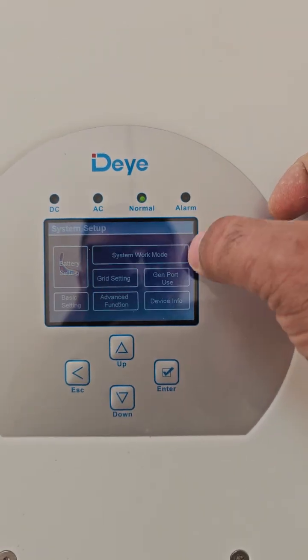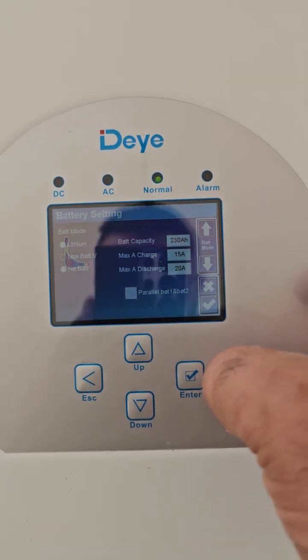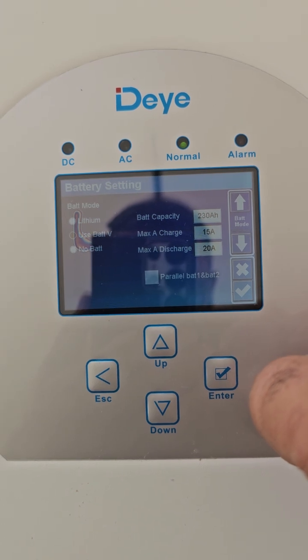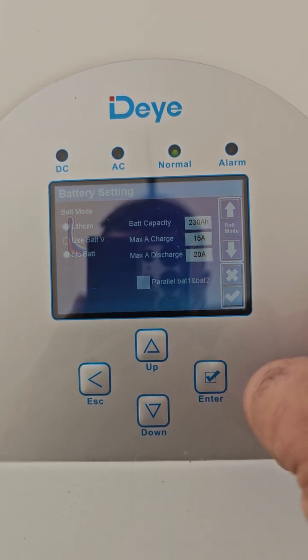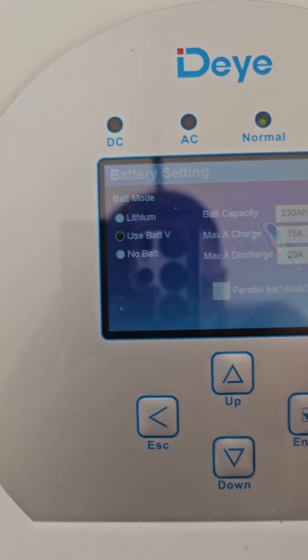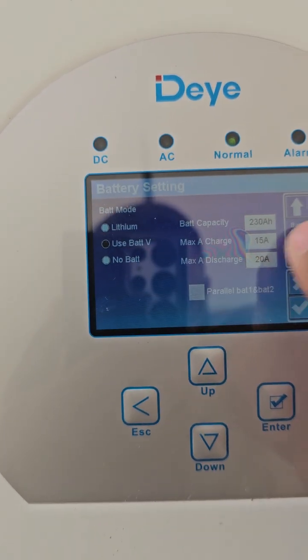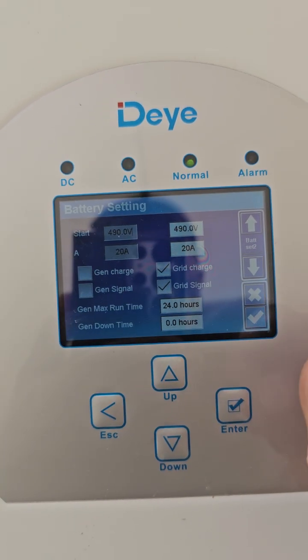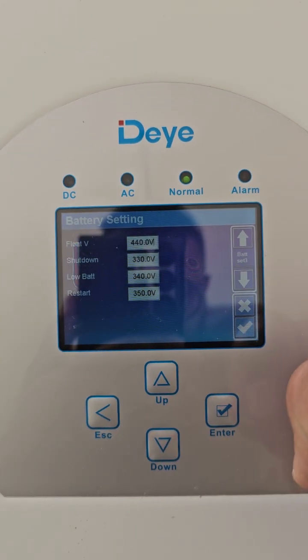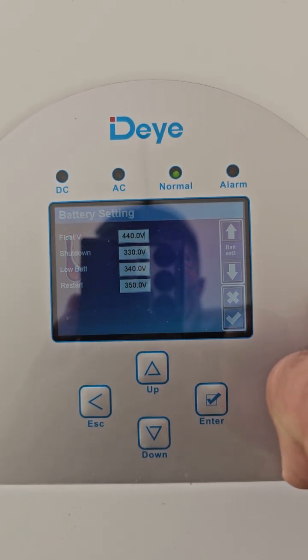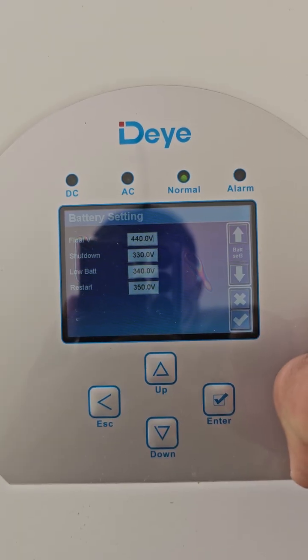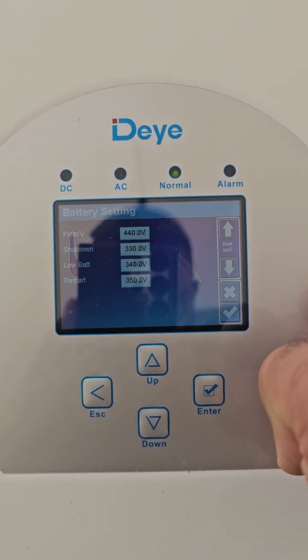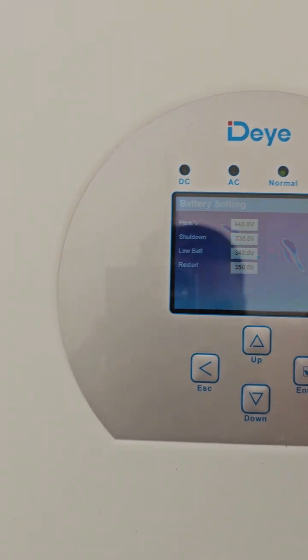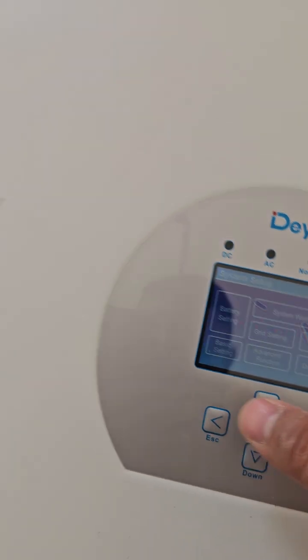When you go to the settings of this inverter, in the battery settings, you can find battery voltage, which uses a specific voltage of the batteries without any communication. On the next page you can set your own values: the float voltage, which is the charging voltage, the shutdown voltage, which is the lower limit, and the low battery restart voltage.